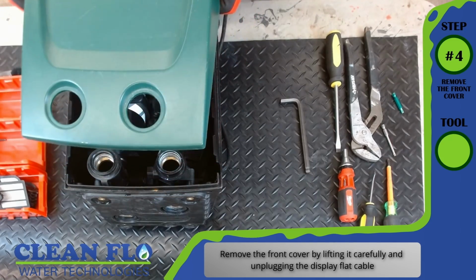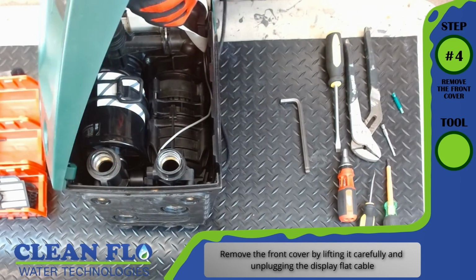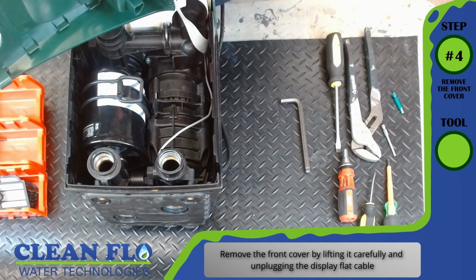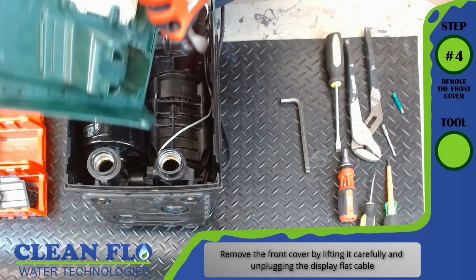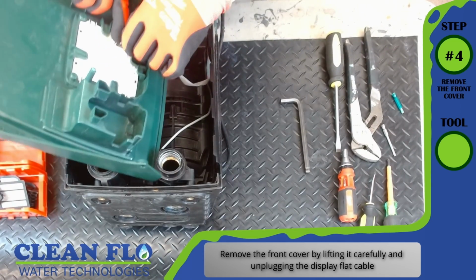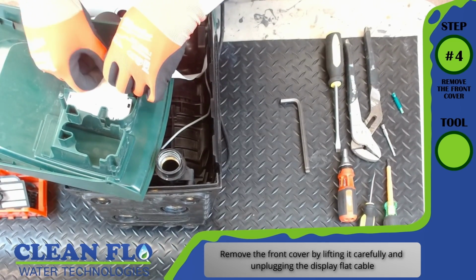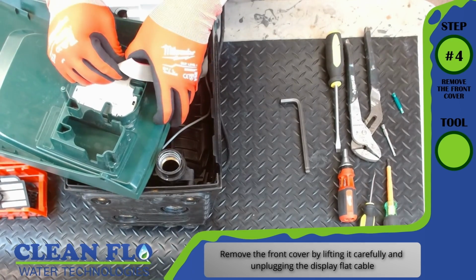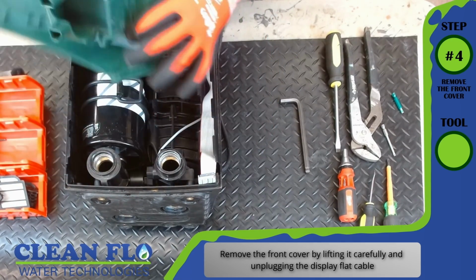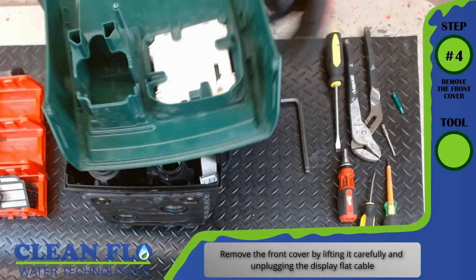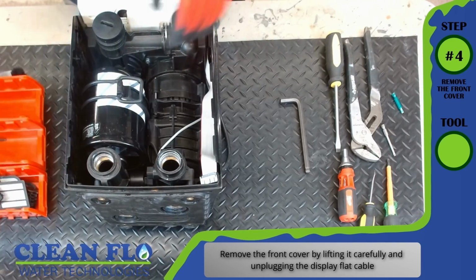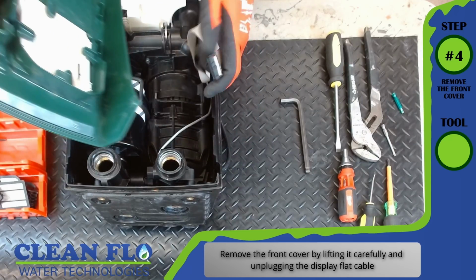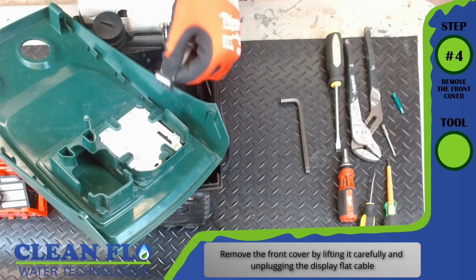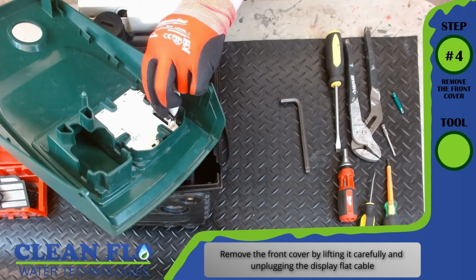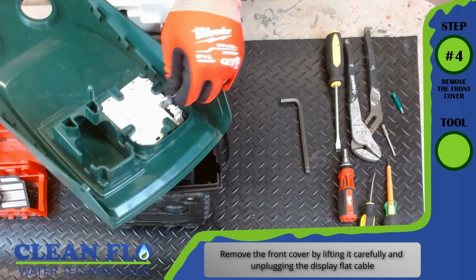Step 4, remove the front cover. You do not require any tools. Remove the front cover by lifting it carefully and unplugging the display flat cable. The display cable is removed by pulling outwards on the two locking prongs and pulling out. This can be done with your fingers and should not require much force. It is keyed so it can be put back in the correct orientation.